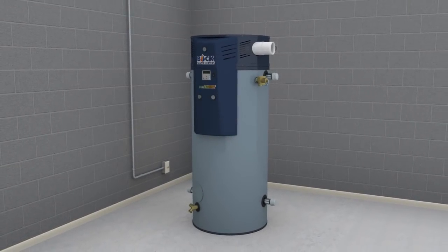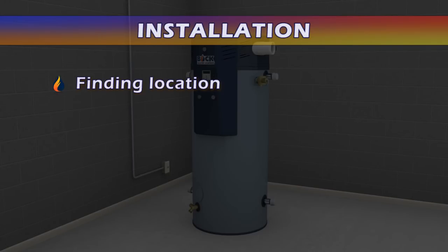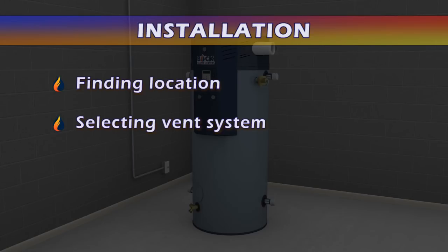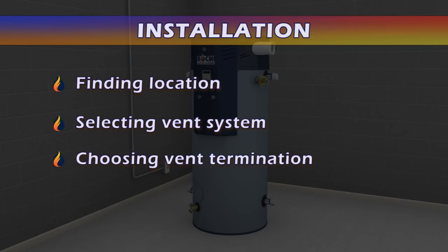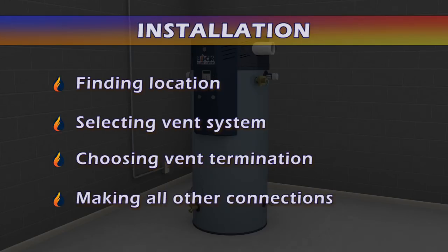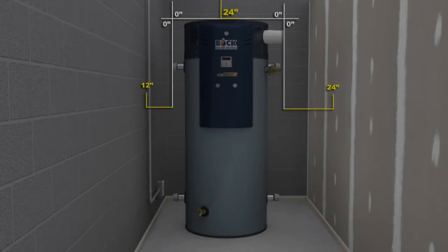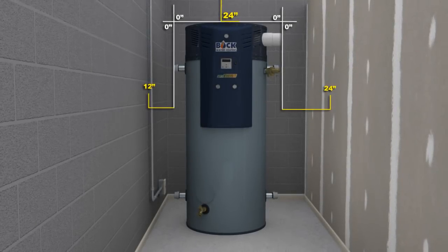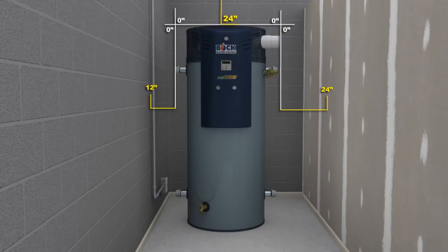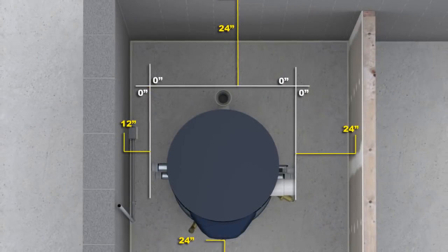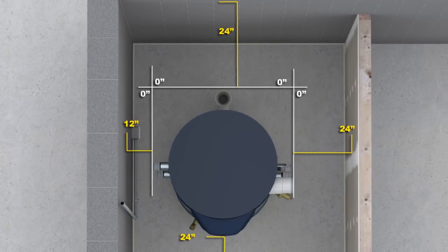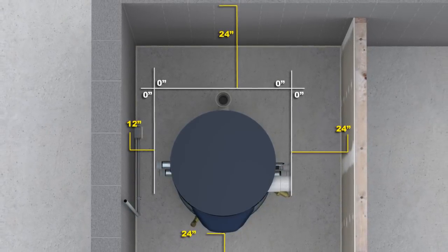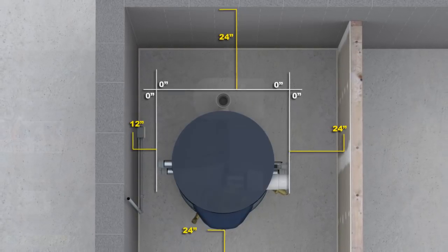Once the model is selected, installation of the water heater involves finding a location, selecting the type of vent system, either a power vent system or a power direct vent system, choosing vertical, roof, or horizontal, sidewall vent termination, and making all other connections. When selecting the right location, the optiTHERM water heater can be installed on combustible or non-combustible flooring. Although the water heater can be installed with zero clearance to combustible materials, it is important that proper clearance be maintained for service and maintenance.